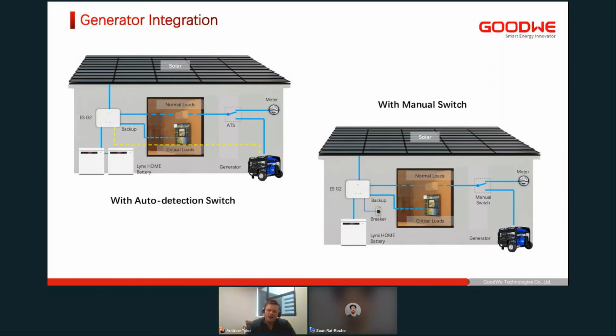And then on the right, you also have an option to do it manually. So you can have a manual changeover switch between the grid connection and the generator. And if you want to top up your batteries, you would manually start the generator and then change that changeover switch from your grid to the generator, and it would then top up the batteries. So there are both options. Maybe you don't want to have auto control because you don't feel like it's the best option. You can have a manual option in this scenario.